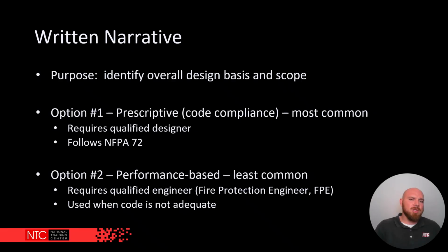Our other option that we don't see performed very often is performance-based design. It's the least common, requires a qualified engineer, somebody that has a fire protection engineering degree. We see performance-based as a requirement a lot of times in specification, but usually it's used when code is not adequate. It's not going to be enough. We need something more than code.